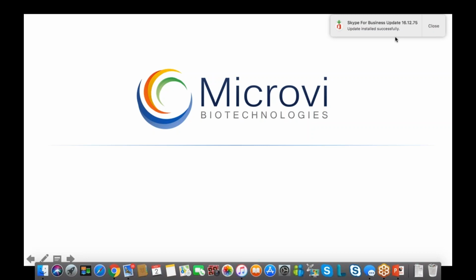Then I have another question, by Mike Russo. The question is, does the biocatalyst require backwashing due to pressure head loss? No, we run our reactors for nitrate as continuous stir tank reactors. If you might imagine, it's a circular tank that's got an overhead mixer. If you've got, let's say, a 10,000 gallon tank, we typically only use a 15 or 20% fill ratio of the biocatalyst.